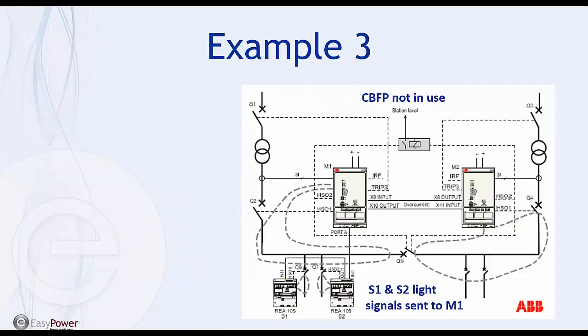Now we're going to look at an example where we're using the optolinks, and this is for a main scheme. In the event that you're single sourcing, you need to transmit the current from one main unit to the other, so the current information can be passed to the REA 105, so when it detects an arcing fault, it can provide trip through the high-speed outputs, which makes it selective. Otherwise, it's the same as what we've seen in example 2.